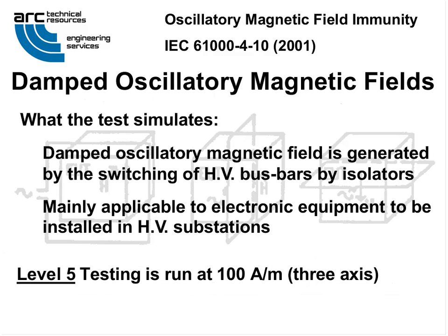Oscillatory magnetic field immunity testing to 61000-4-10. Damped oscillatory mag field test simulates the magnetic fields generated by the switching of high voltage bus bars or isolators. The test mainly applies to electronic equipment that's installed in high voltage substations. Level 5 testing is required inside the fence, level 4 outside the fence. That's 100 amps per meter for 2 seconds, each waveform in all 3 axes. 1/10 of that outside the fence, 10 amps per meter.